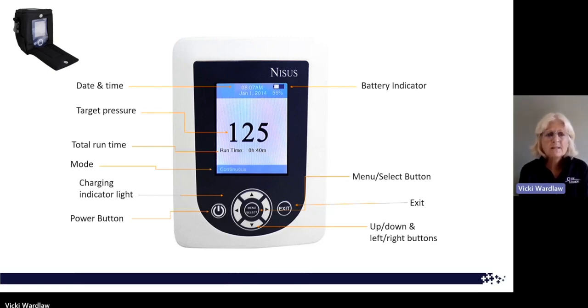Total runtime sits underneath that target pressure. That's the hours and minutes that particular device has been on that patient. It will come with 0 hours, 0 minutes, and when you put it on your patient and turn it on for the first time, it will start tallying up the hours and minutes, which is really helpful if you're trying to determine if the device is being turned off, if you're missing hours on there in between dressing changes. This is where you would go to look and see if in fact that is happening.